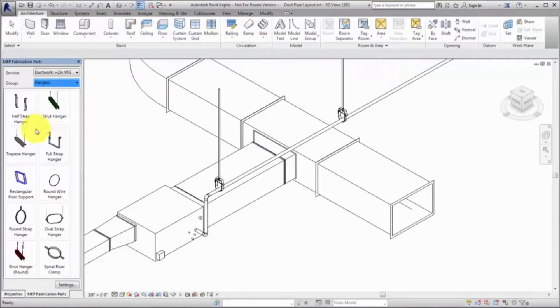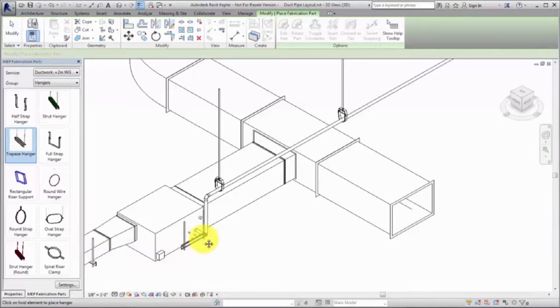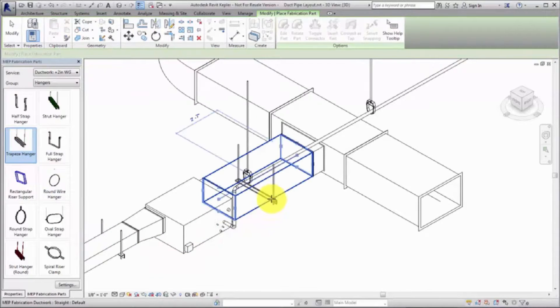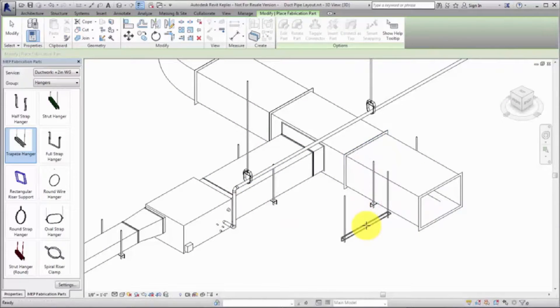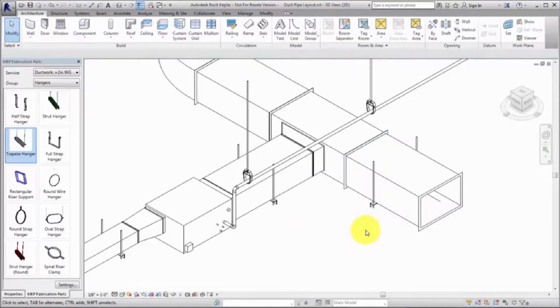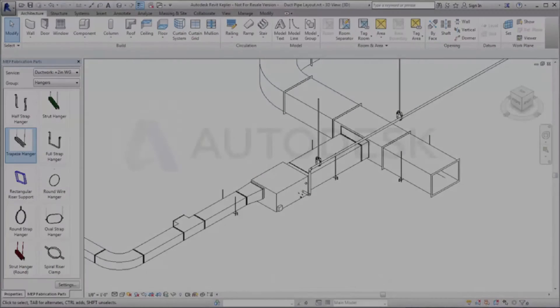By default, hangers are attached to the closest structure element. Structure categories include floor, roof, structure framing such as beam or truss, stairs, and slabs. If no structure element is available, Revit uses the default rod length as set in the ITM file definition. When you use Revit to create a fabrication model, you can achieve a higher level of development.